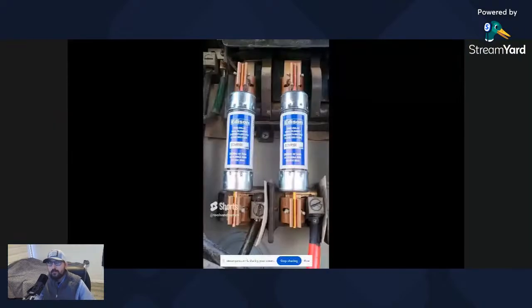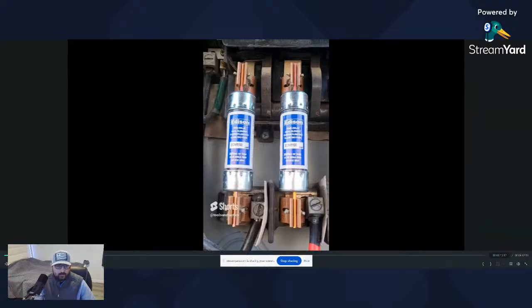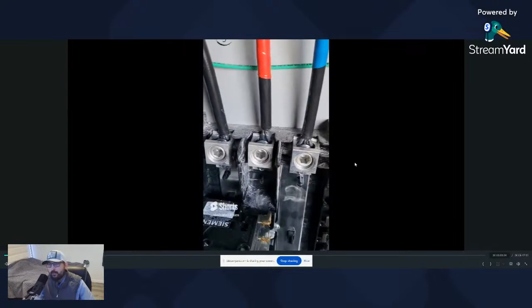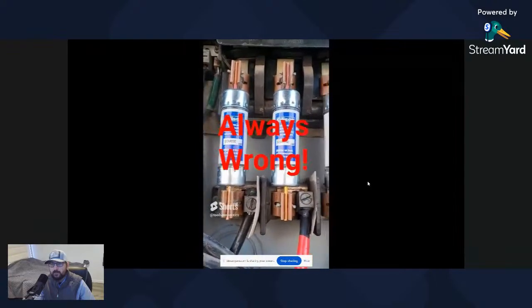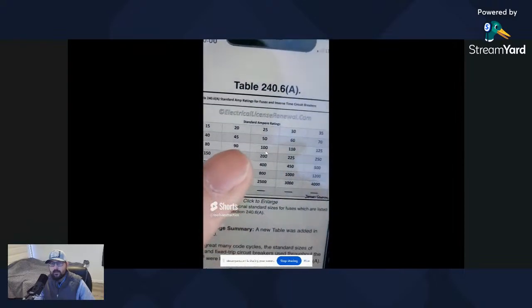There, so you see we got 100 amp fuses here. And if we go back just a touch, you see that number 2 wire is good for 90 amps on 100 amp fuses, and that's something common. So then we've got our 240.6 there—you can see 90 degrees C right there, or 90 amp rating on the 75 degree C column. No good. And then we show you here again, 90 amps on 75 degrees C. Some of these I've got the code up in the shorts, some of them I don't.